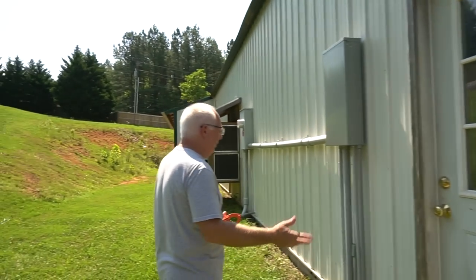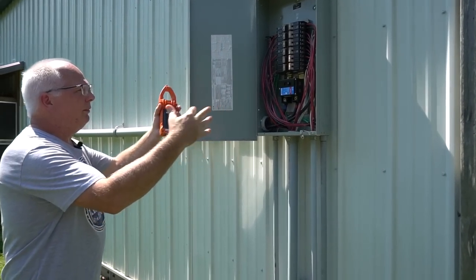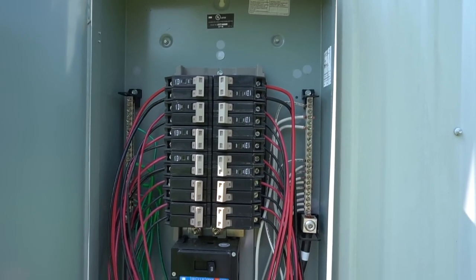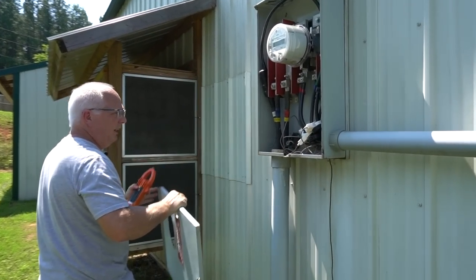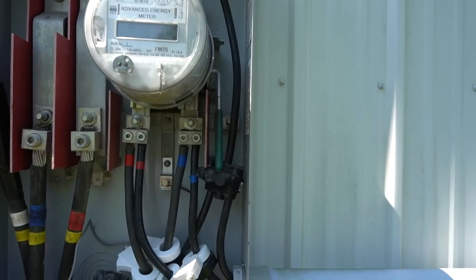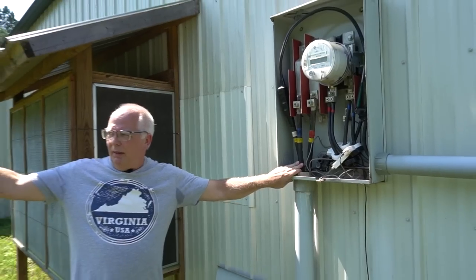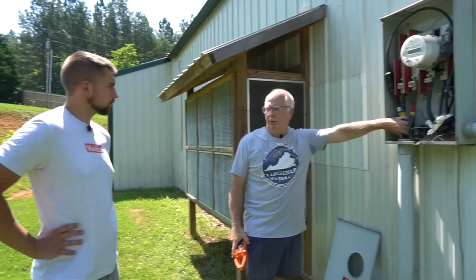Here is a sub panel that basically combines all the AC power from all the panels into a single feed that goes over into the meter base. These are big 500 MCM aluminum cables that run up to the main residence and that splitter we saw before. Being that these are 500 MCM, it keeps the voltage drop very low — maybe one and a half to two volt drop, so it runs about 250 volts.